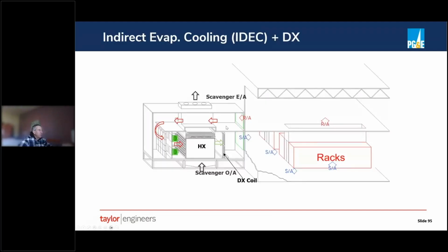Okay, another type of economizer, if you will, is indirect evaporative cooling, or another type of evaporative cooling is to use indirect rather than direct outside air. So instead of humidifying the outside air directly, you can humidify outside air that's passing through a heat exchanger, and that will cool down the air passing through the other side of the heat exchanger. So this is sort of a schematic of an indirect unit that we worked on for a data center. It's basically just recirculating return air through this heat exchanger.